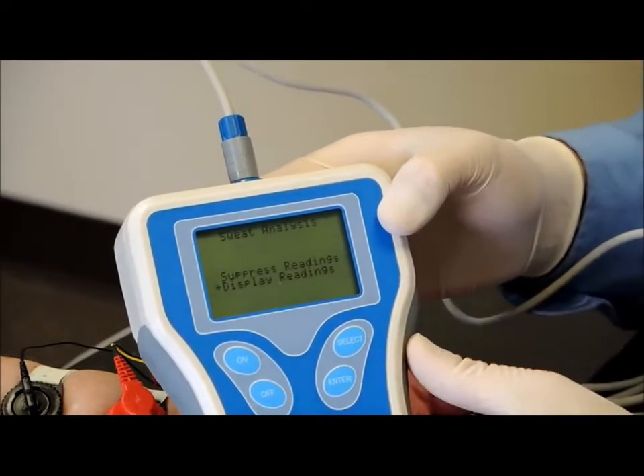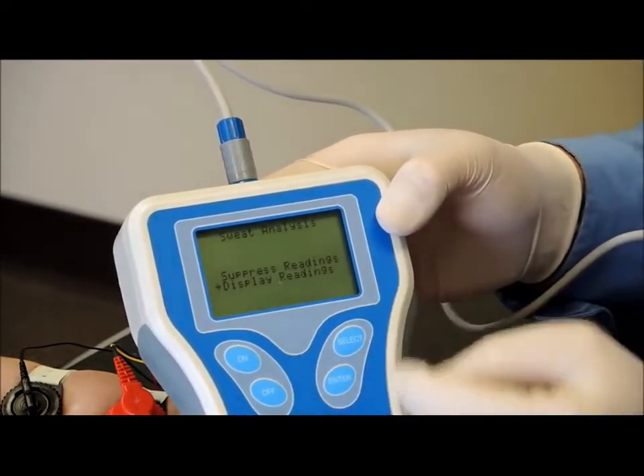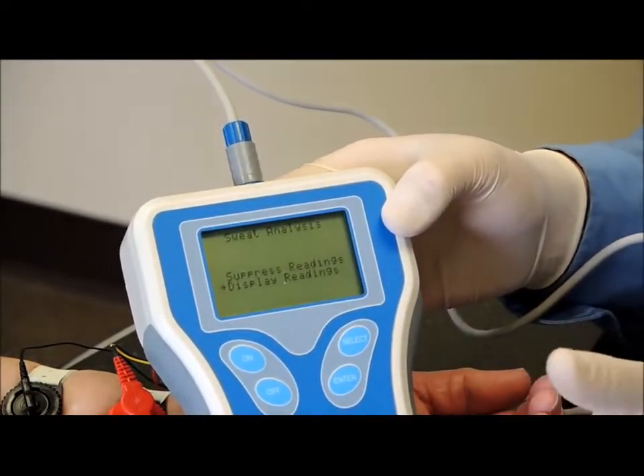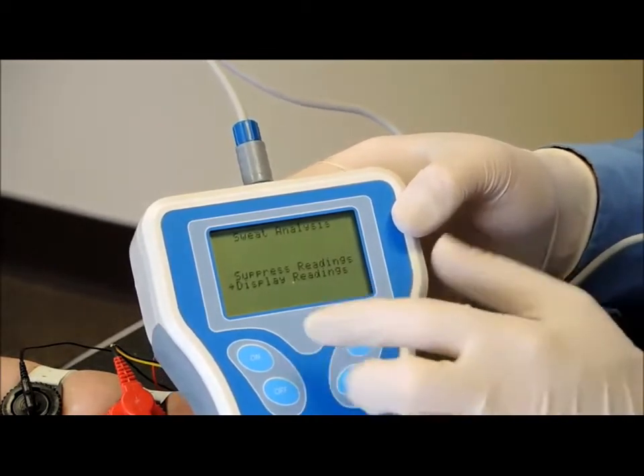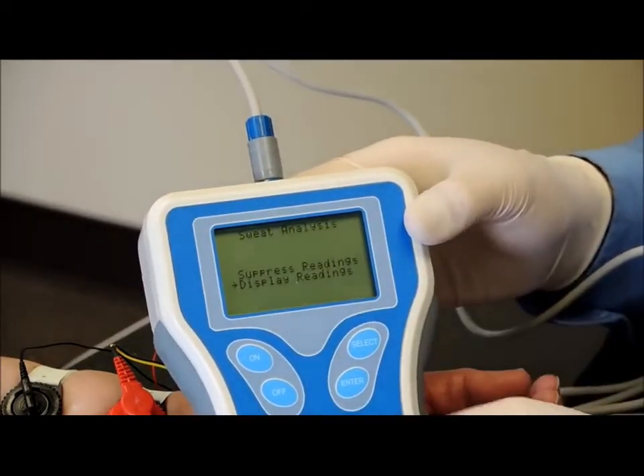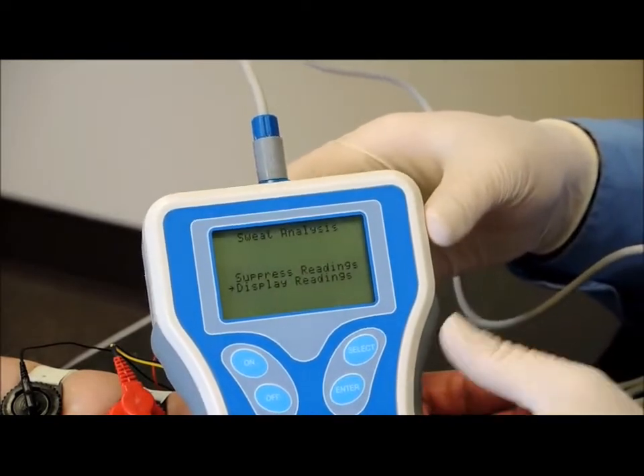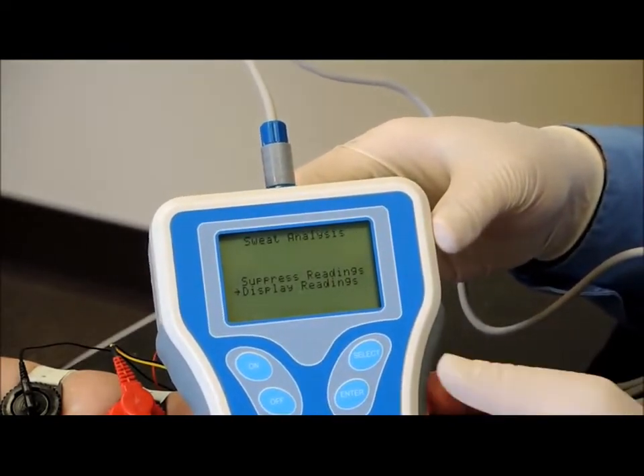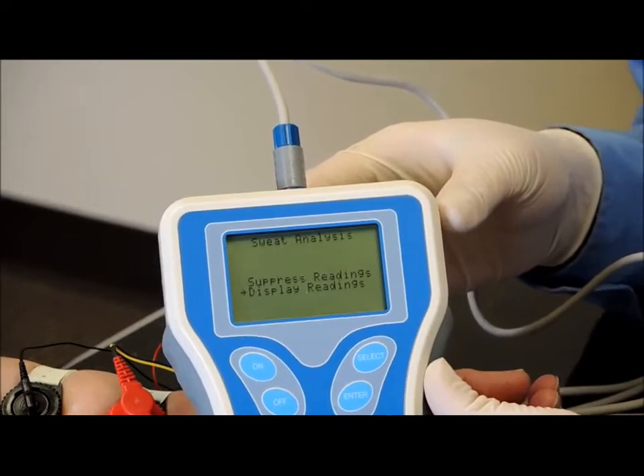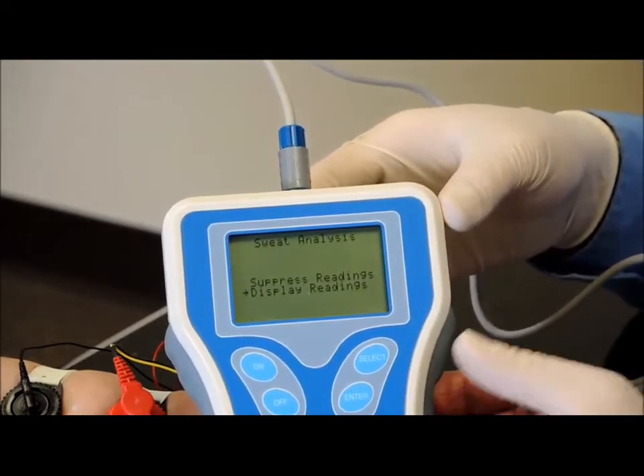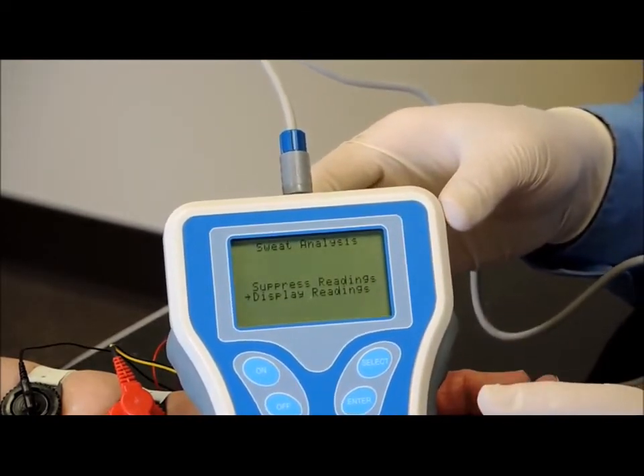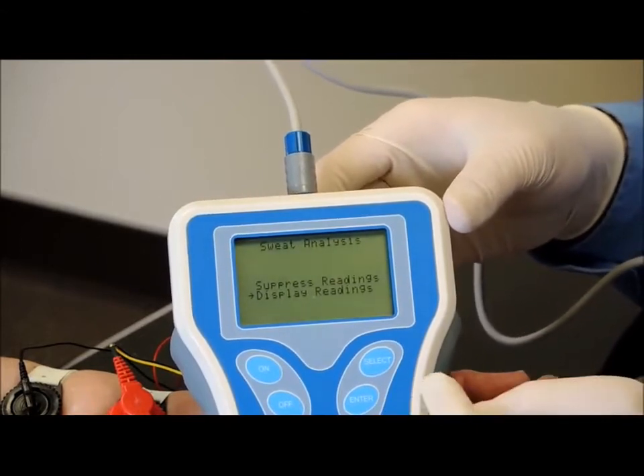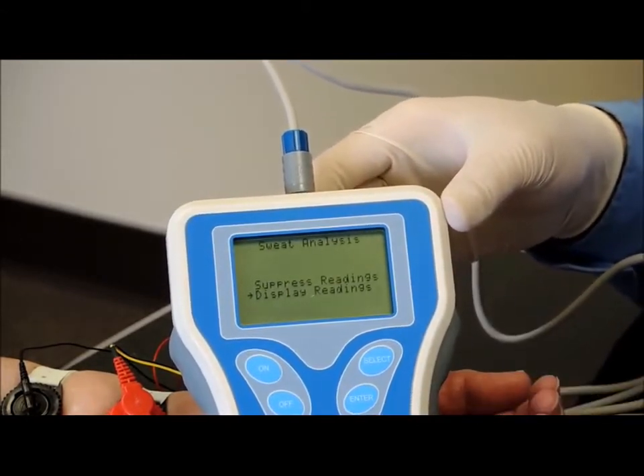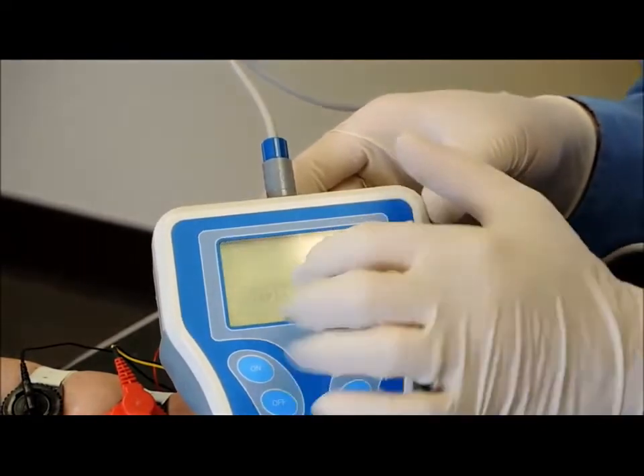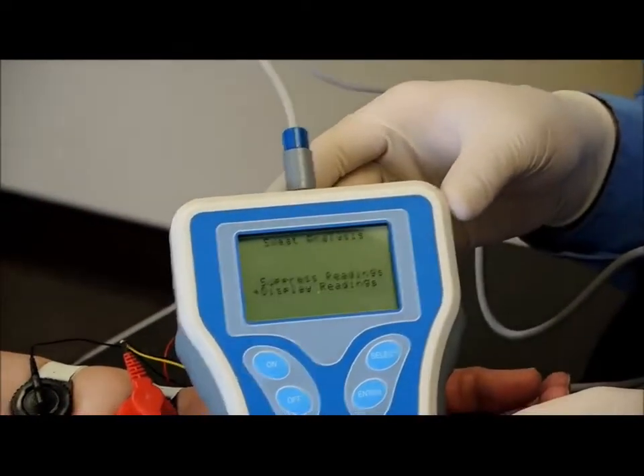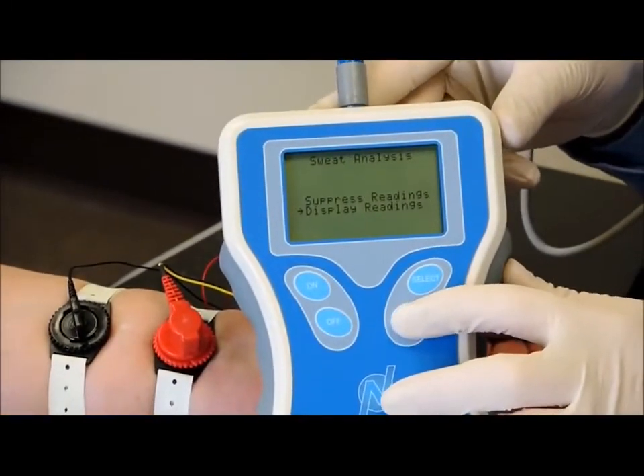You have the choice to display the reading or suppress the reading. In most clinical applications, you'll choose to suppress the reading. That will mean that there are no values being shown on the screen during the analysis. You don't have parents looking over the shoulder saying, "Oh, what's that? What does that reading mean?" If you're just doing a demonstration, you may choose to display reading. In this case, I'll choose display reading. The arrow is pointed towards display reading. I'll choose enter for that.